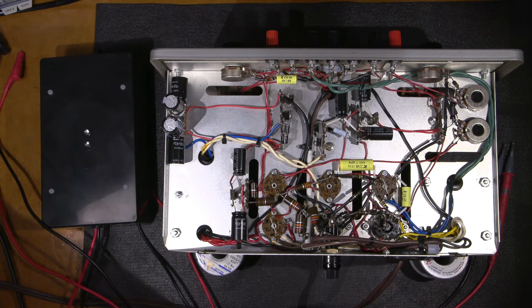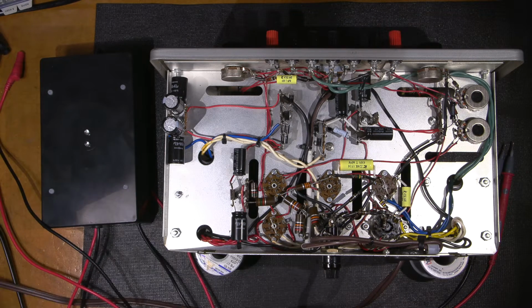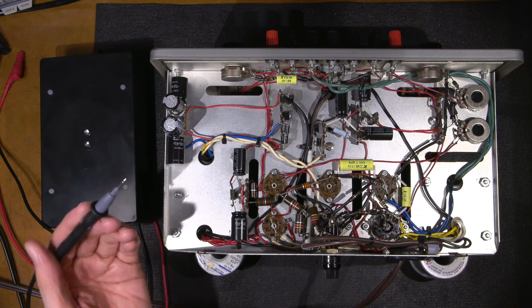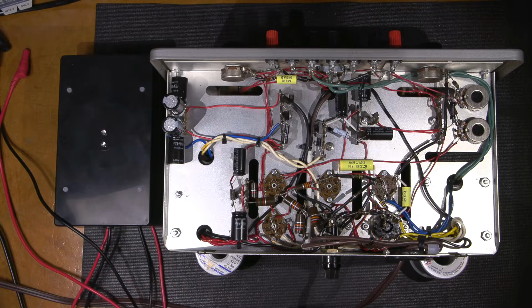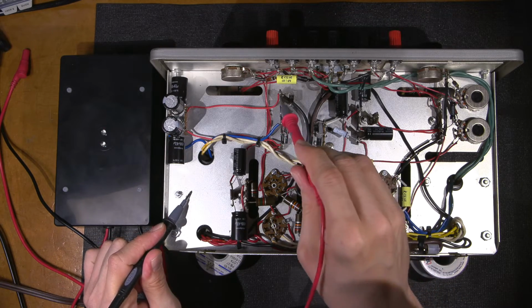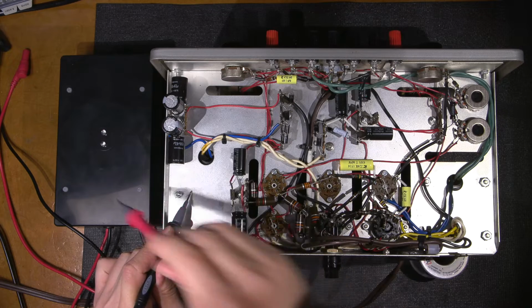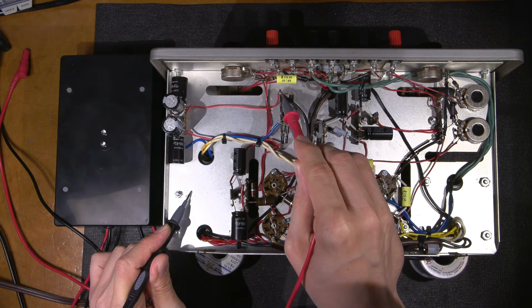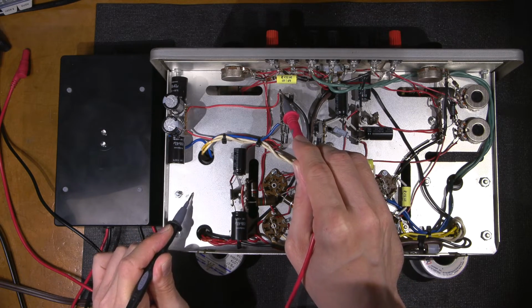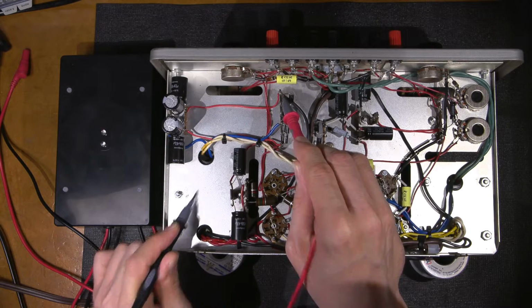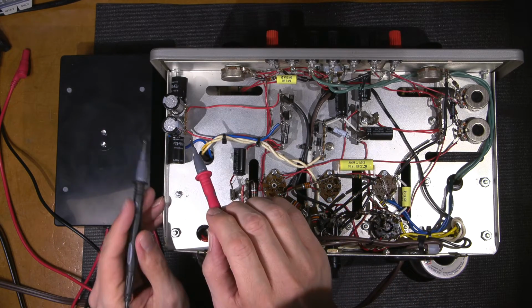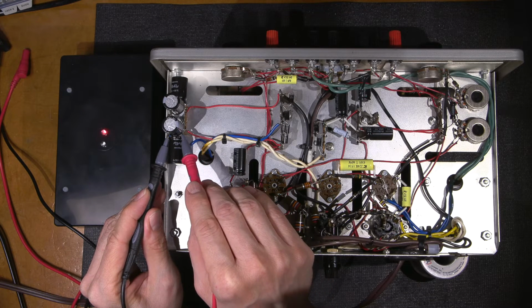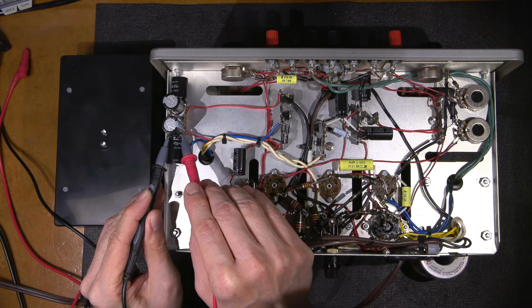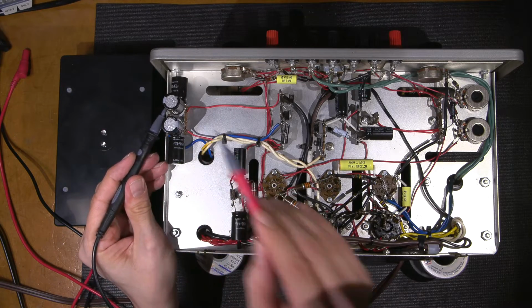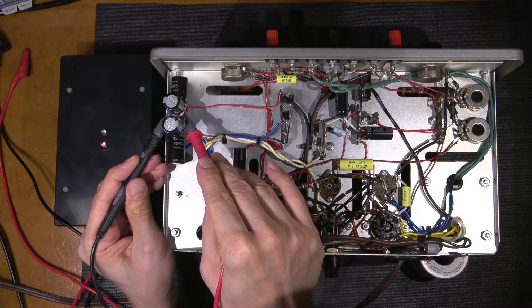I'll hit the power supply here and turn it back off. All right, so everything's going to be charged up, at least in the diode supplies here. So again, with the discharge device, keep an eye on the LEDs here. I'm going to go right to the positive of the stack. So the 600 volts right here, right? Watch the LEDs. Look, nothing's happening. Right to the chassis, see that? Now look what happens when I go across the capacitors. See that? I'll go across this one here. Look at that.